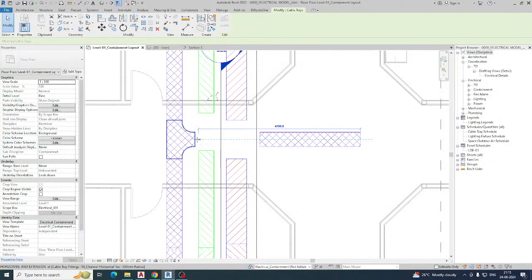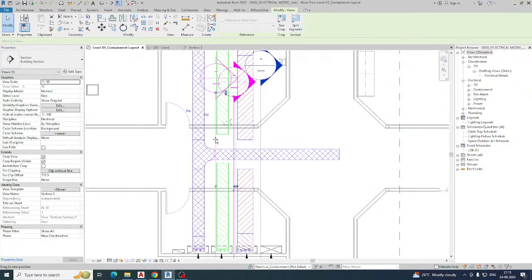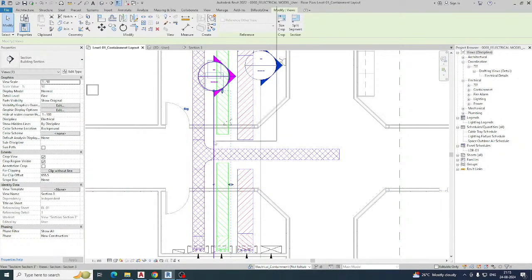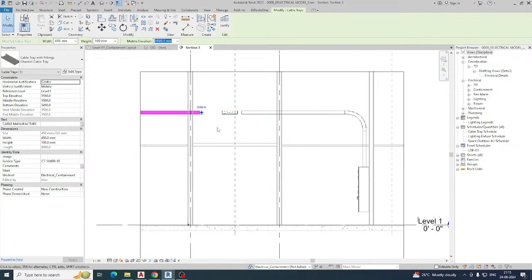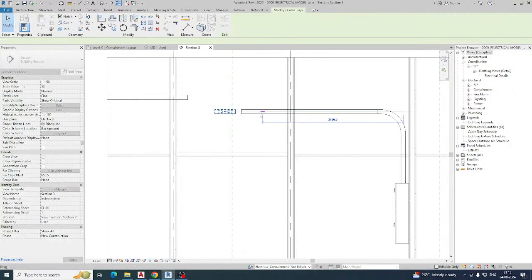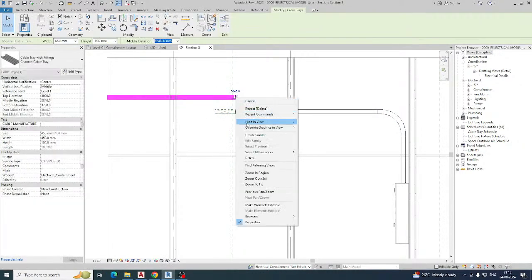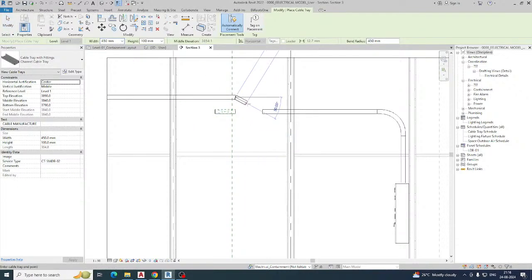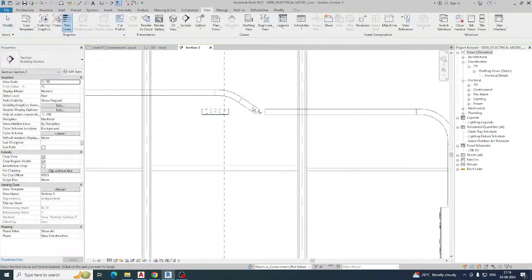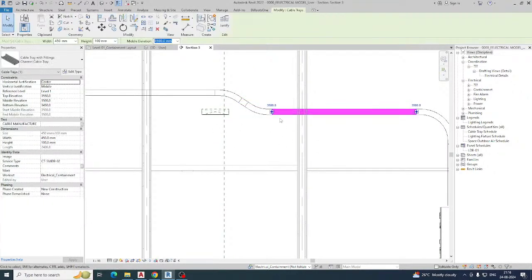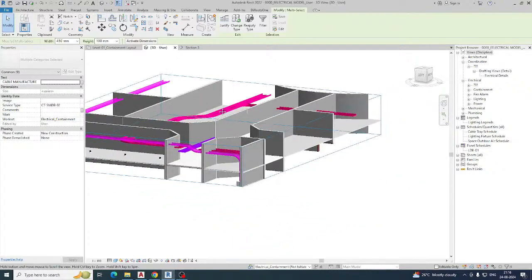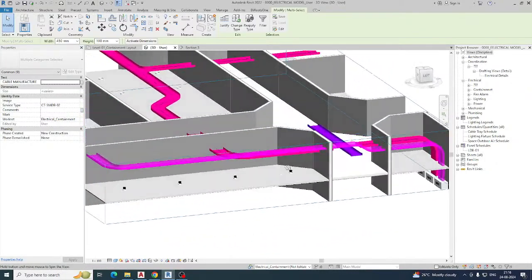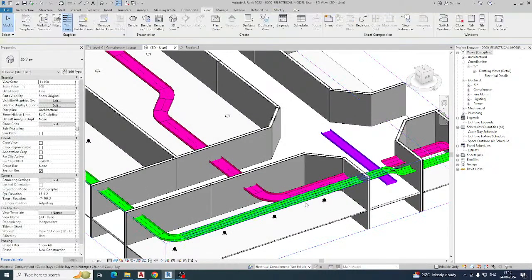To avoid the clash, you need to reroute without overlapping. In the section view, you can see it was clashing with another cable tray. Make that section of cable tray a little bit higher — raise it by a certain height — then move it back and stretch it. Draw a new cable tray using Create Similar, trim to connect, then verify in the section view that it goes at a different level and avoids the clash.